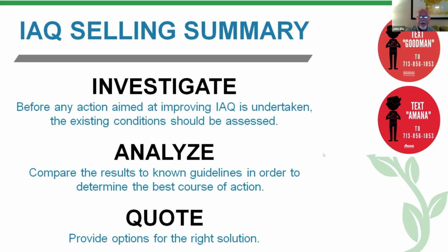If we have high carbon dioxide, one, we always want to look at source. If we can do source control, that's great. But what can we do to offset that? If we're looking at high carbon dioxide, identify the source, and that's probably going to tell us that maybe we ought to look at dilution as the answer to the problem, and that would be bringing outside fresh air in to dilute and or change building pressures to take care of that type of problem.